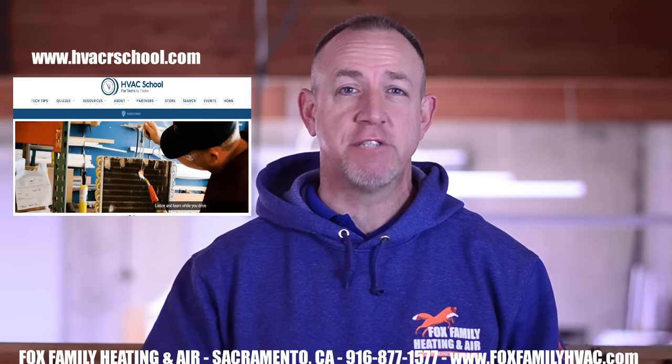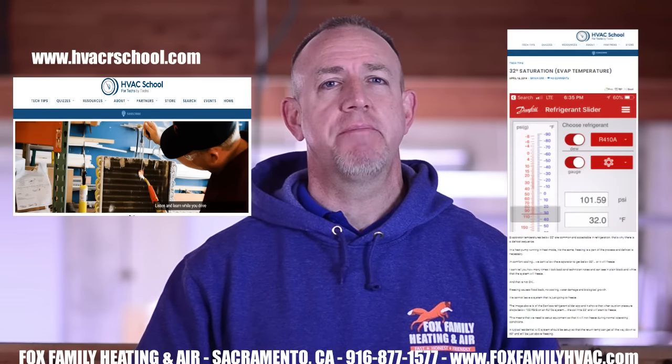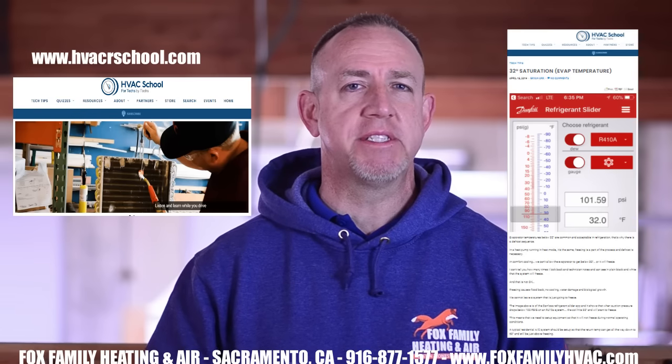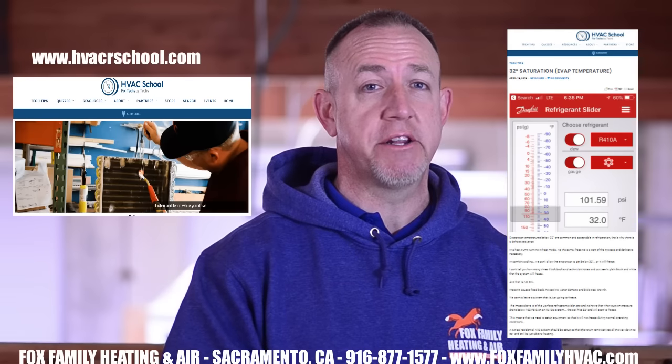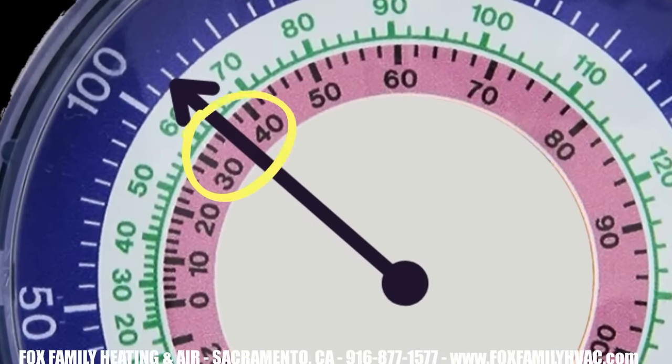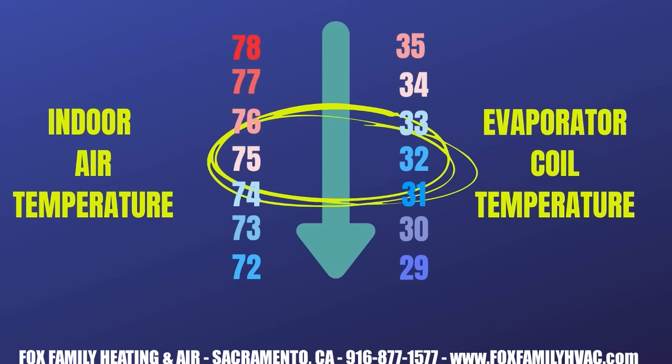I like what Brian Orr from HVAC School mentioned in an article I read. He said we need to set up the equipment so that it won't freeze during normal operating conditions. At the very least, the typical residential AC system should be set up so that the return air temperature can get all the way down to 68 degrees and still be just above freezing at the evaporator coil. For example, at 78 degrees in a house on a 410A system with a suction pressure of 118 psi, your suction saturation coil temperature is 35 degrees, so the coil won't freeze. However, the coil temperature will drop approximately 1 degree for every degree the return air temperature drops. So if the customer sets it down to 74 degrees, the saturation temperature would get all the way down to 31 degrees and the system will start to freeze up.